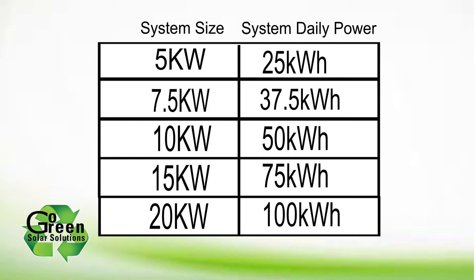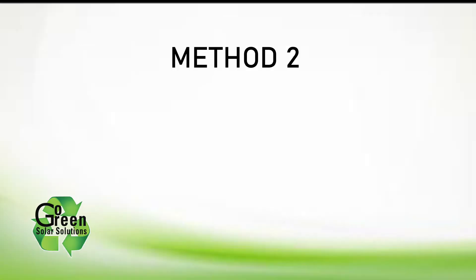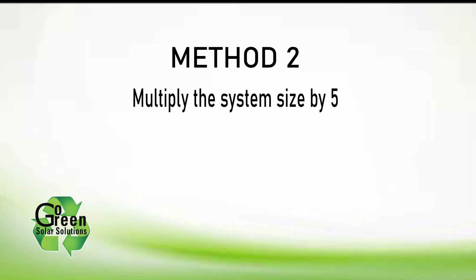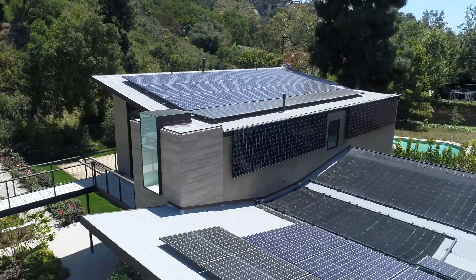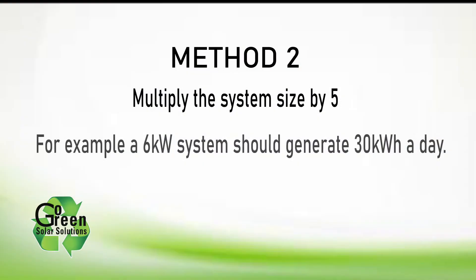Here are some examples of system sizes and how many kilowatt hours they will be producing per day. If your system is within 10% of these numbers, then your system is working well. Older systems will lose 1-2% per year. Another way to know how much power your solar system should be producing is by multiplying the system size by 5 — that's roughly the number of kilowatt hours your system should be generating. For example, a 6 kilowatt solar system should generate roughly 30 kilowatt hours per day.